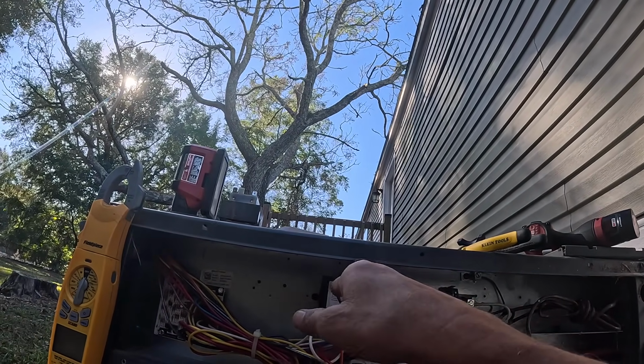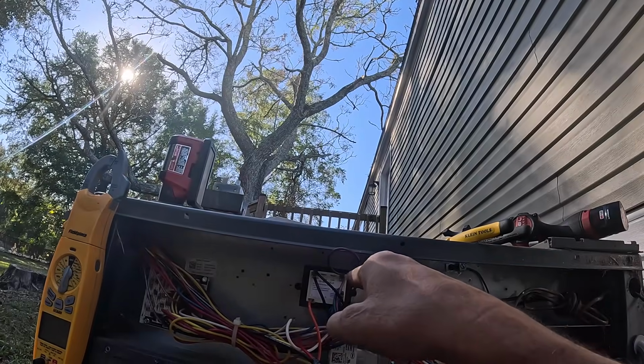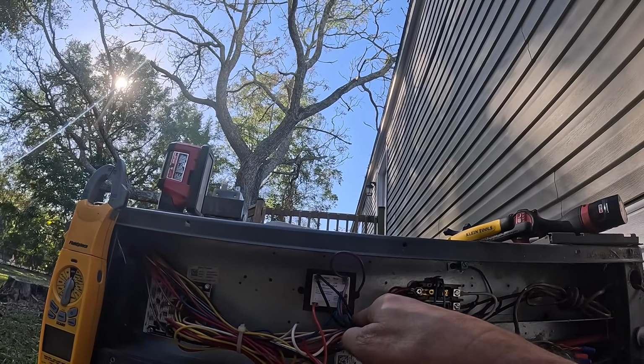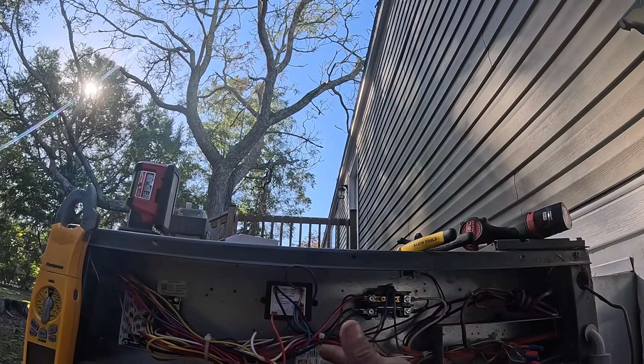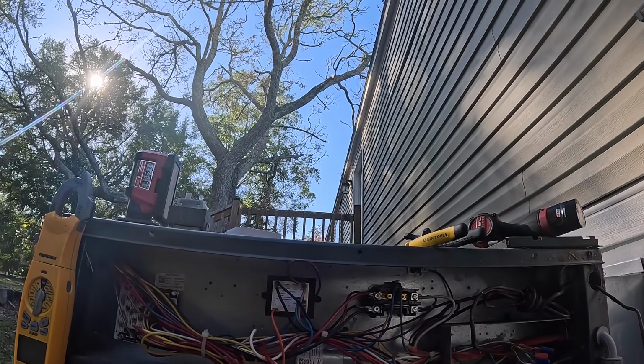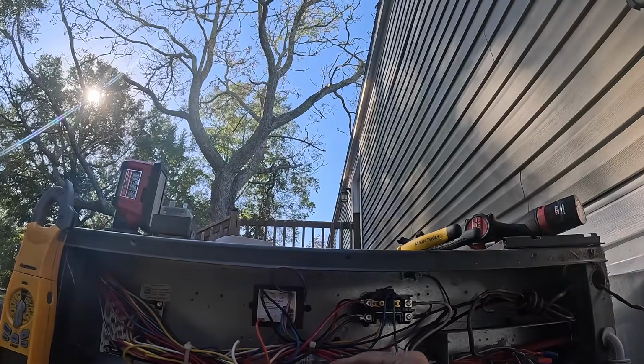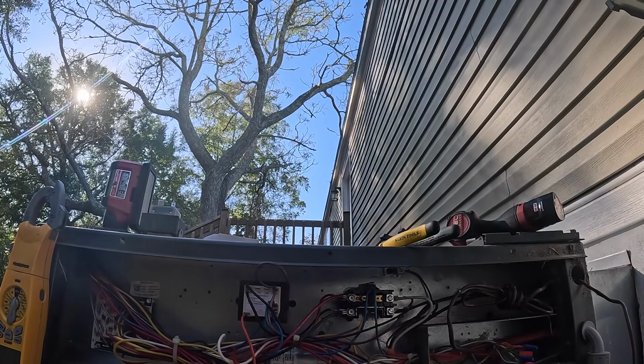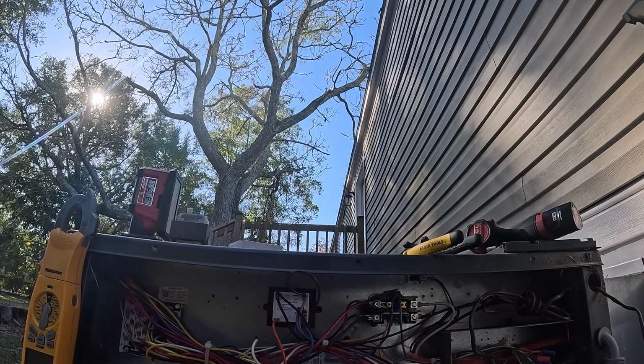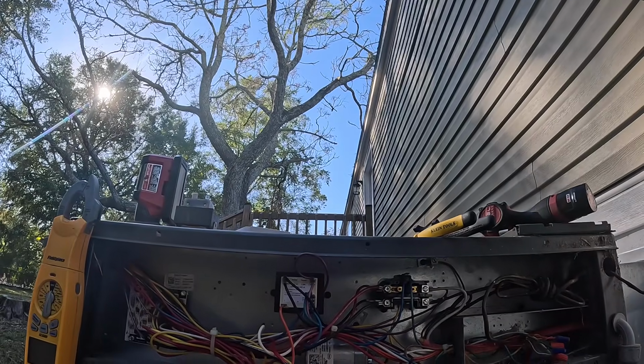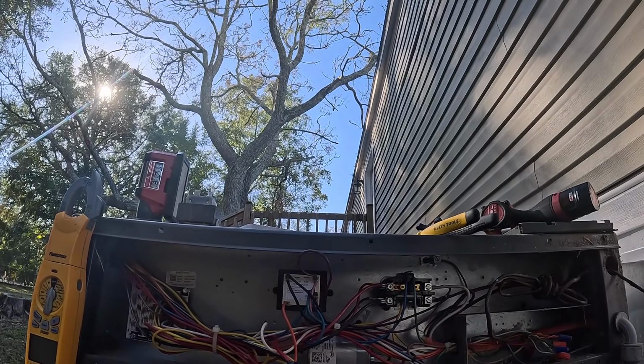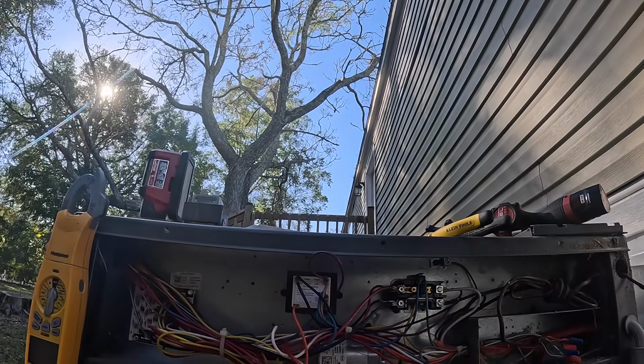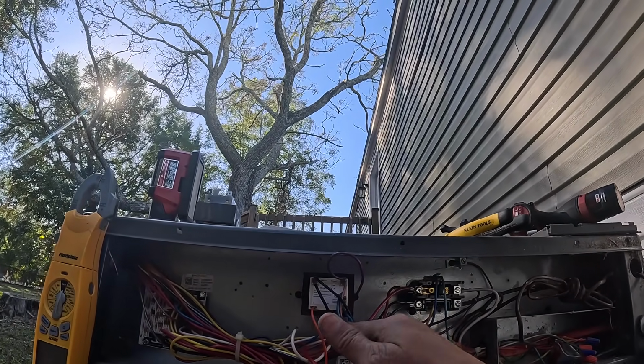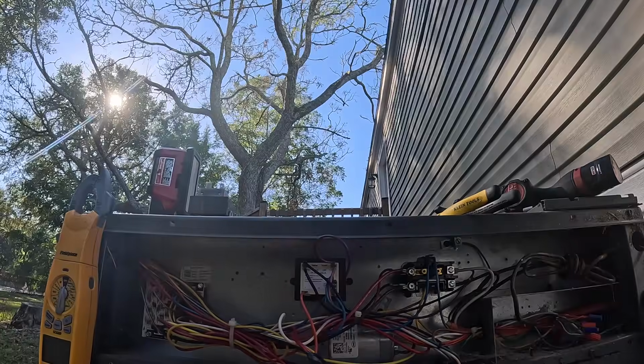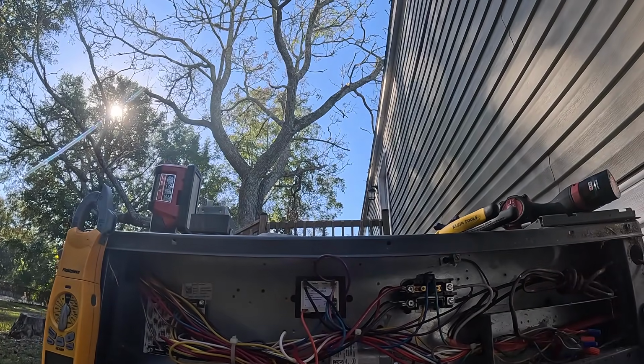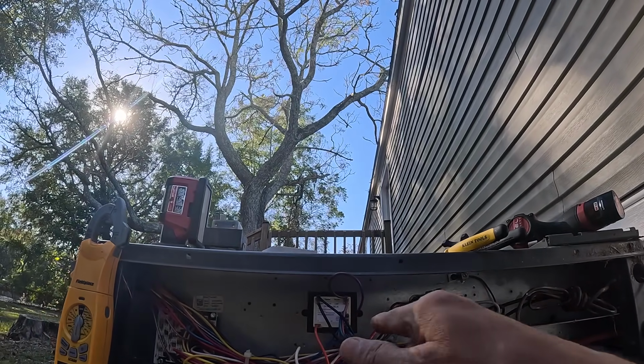So this up here is going to be 240 volts, and this right here on the bottom is what produces our control voltage, or low voltage, 24 volts. That's much safer to run in the house to a thermostat. Line voltage thermostats can cause fires in the house; I've worked on a few of them, and honestly I think they're a little dangerous. A low voltage thermostat may spark a little bit, but it's much less likely to cause a fire. So we use low voltage.